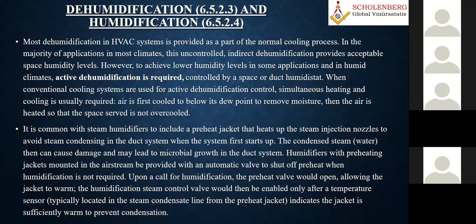Then some of the sections talk about what type of dehumidification and what type of humidification you have to do. Generally, dehumidification is done in the cooling coil, depending upon the ADP you take in the design. But for humidification, we always use steam humidifiers, because you always put in some preheat jacket that heats up the steam injection nozzles and prevents the steam condensing in the duct system.